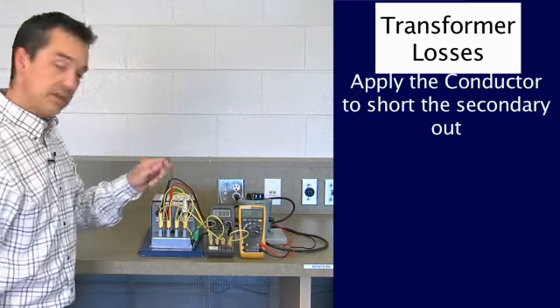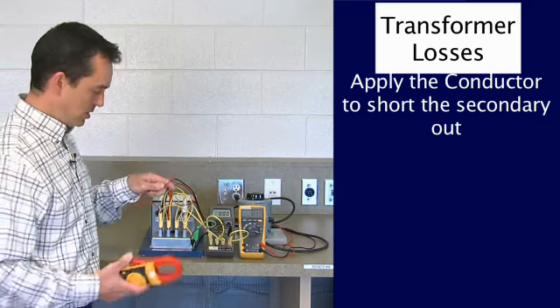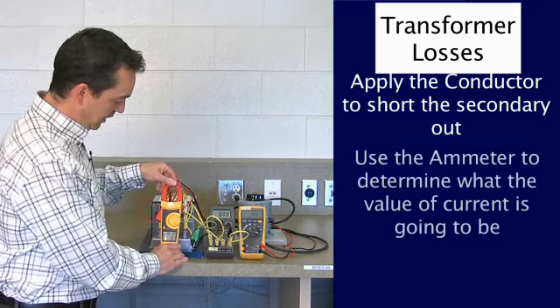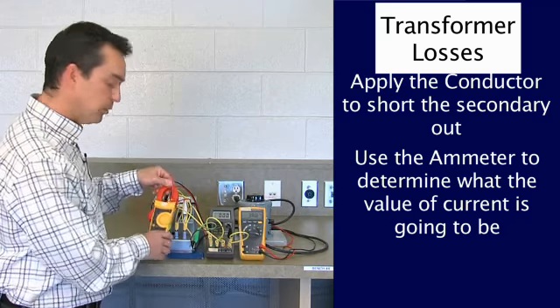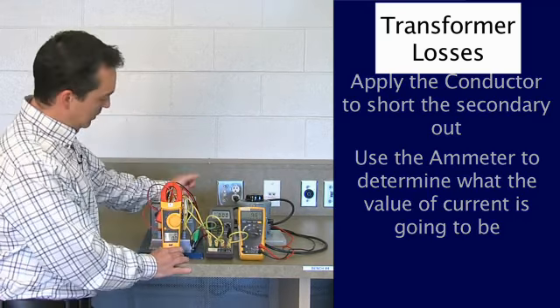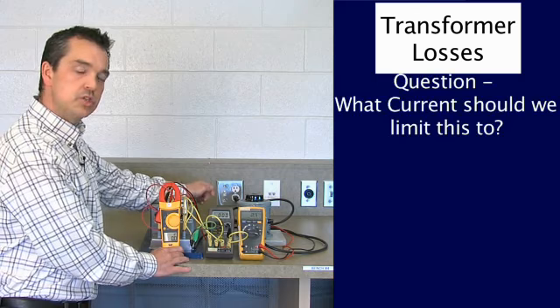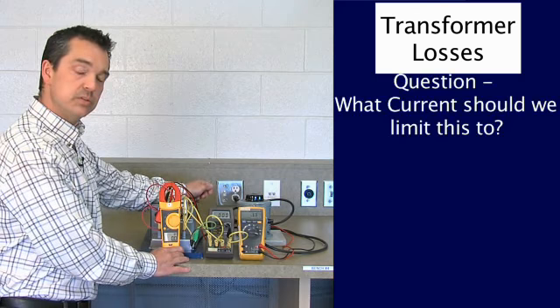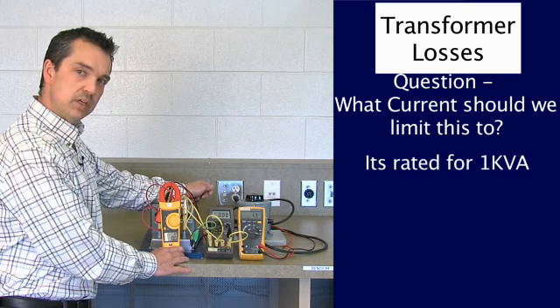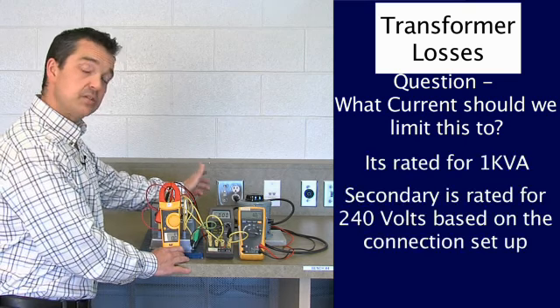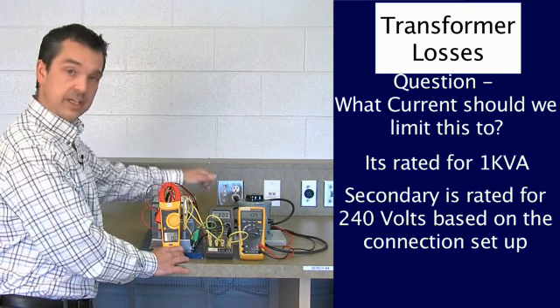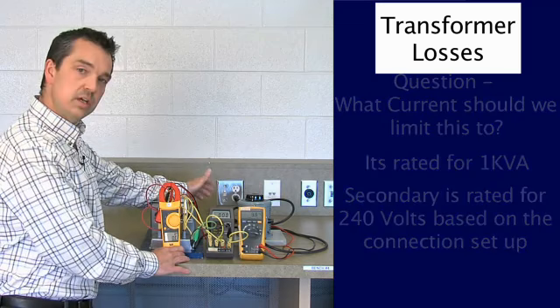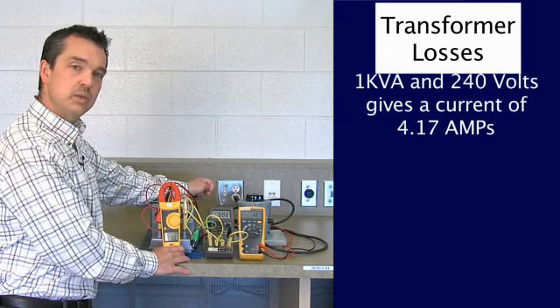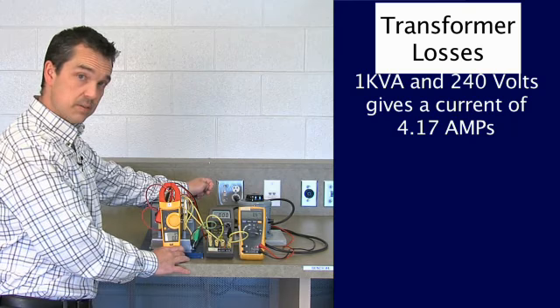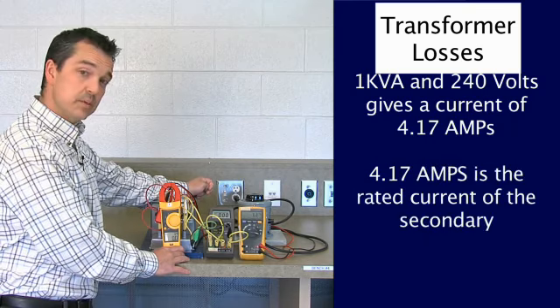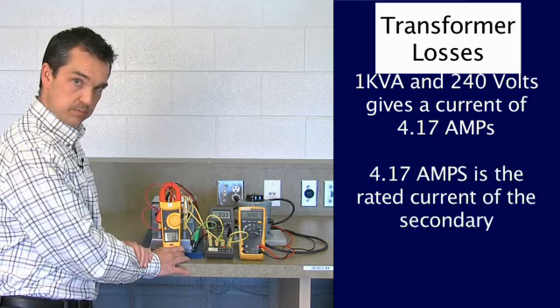So I've just used a conductor to short the secondary out, and I'm using an ammeter to determine what the value of current is going to be. The question is going to be asked again, what current should I take this piece of equipment up to? And it's rated for 1 kVA. My secondary is rated for 240 volts based on the connection that I have. So 1 kVA and 240 volts would give me a current of 4.17 amps. So if it's 4.17 amps, that's what I'm going to take this meter up to.